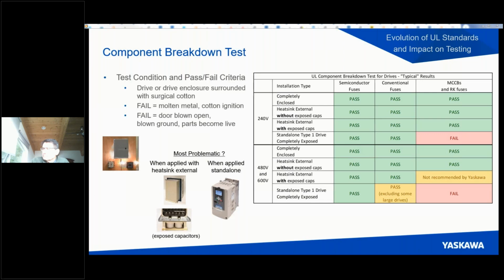Another area I want to point out is the yellow cell at the bottom of this chart. In most cases, conventional fuses will protect a standalone drive. However, some large drives mounted in this way must be installed with semiconductor fuses, and Yaskawa has special kits available for these conditions.